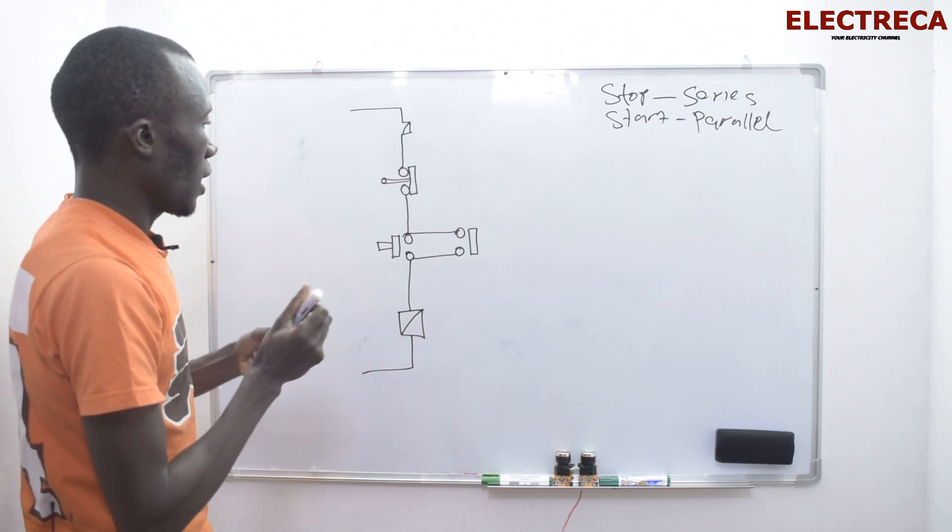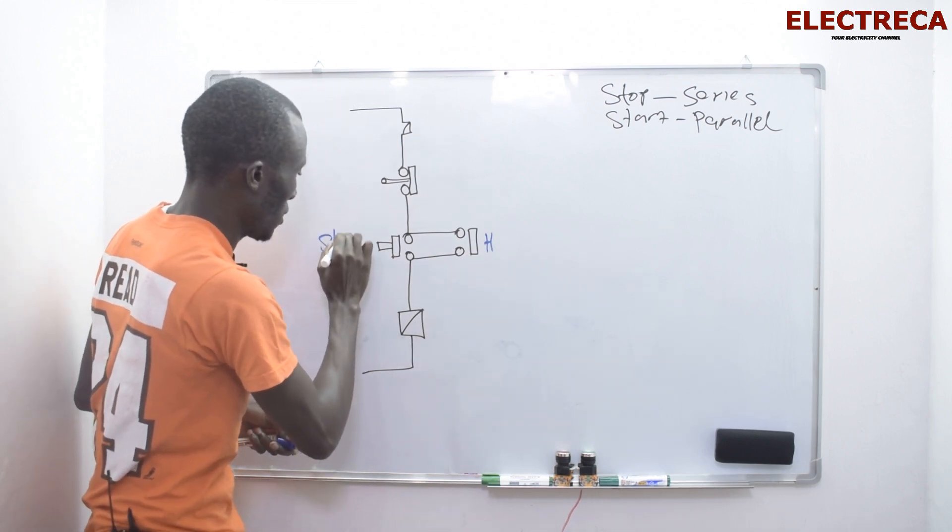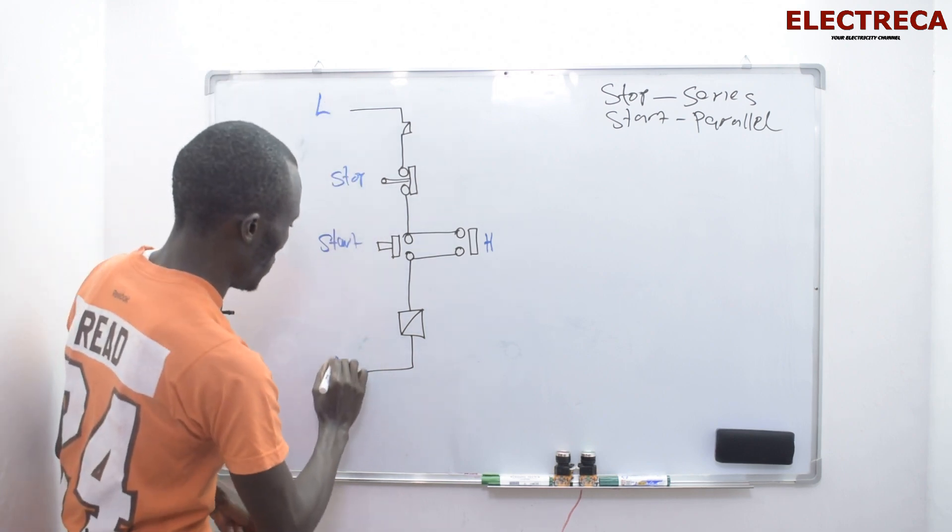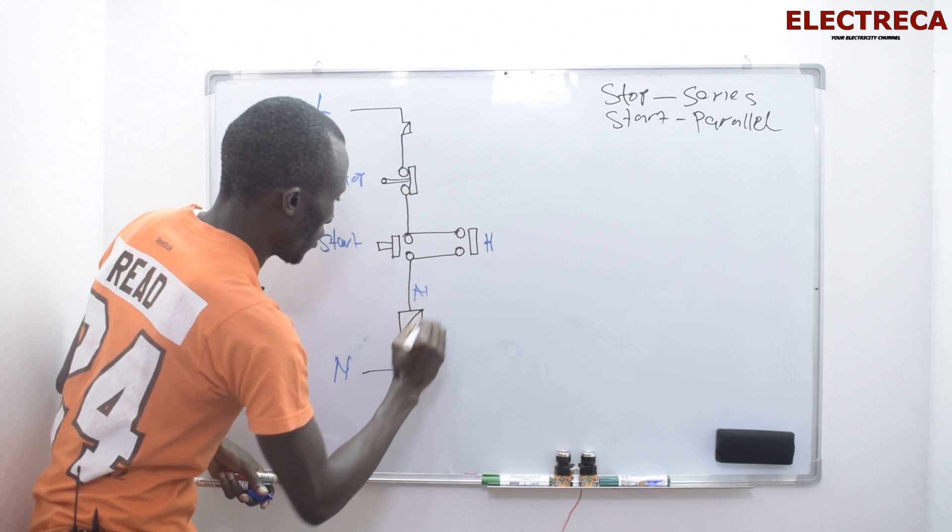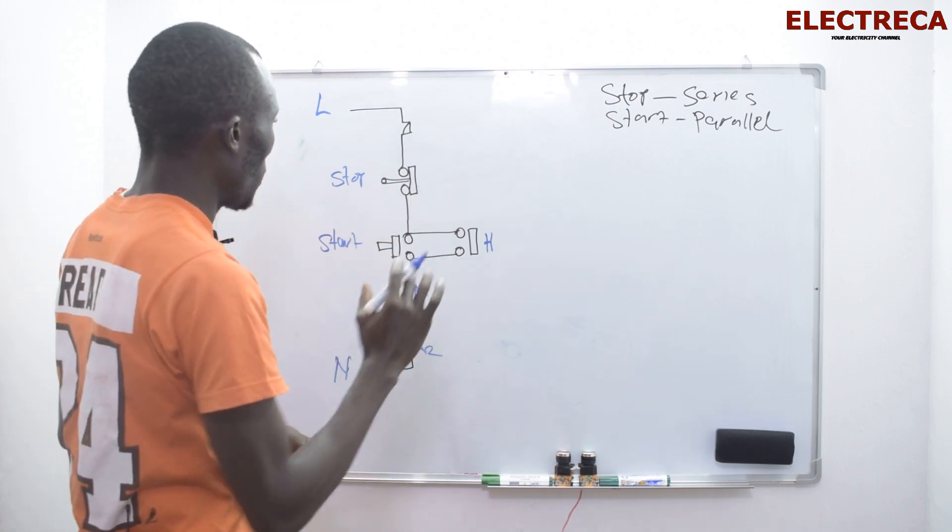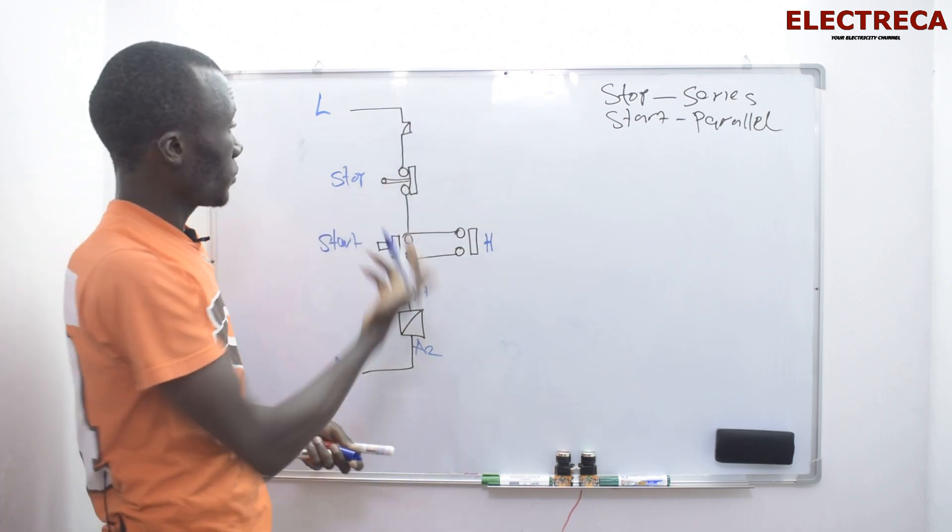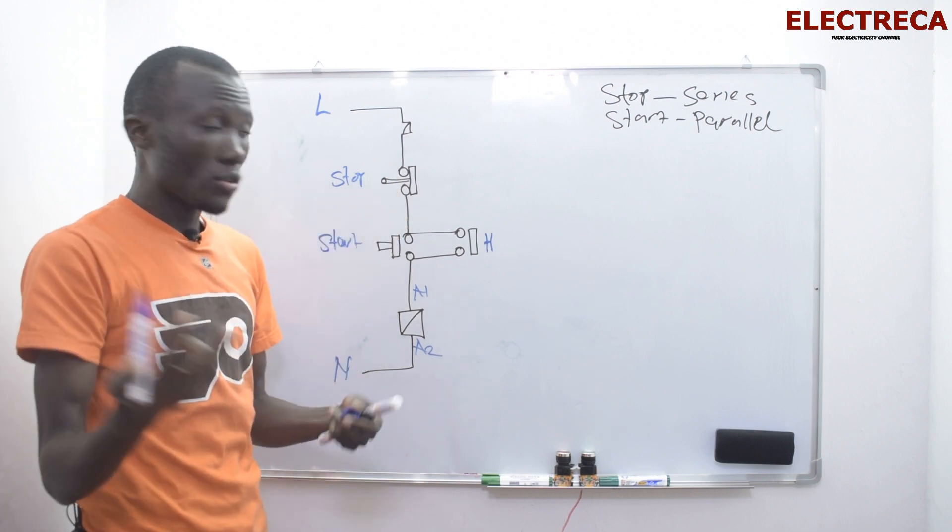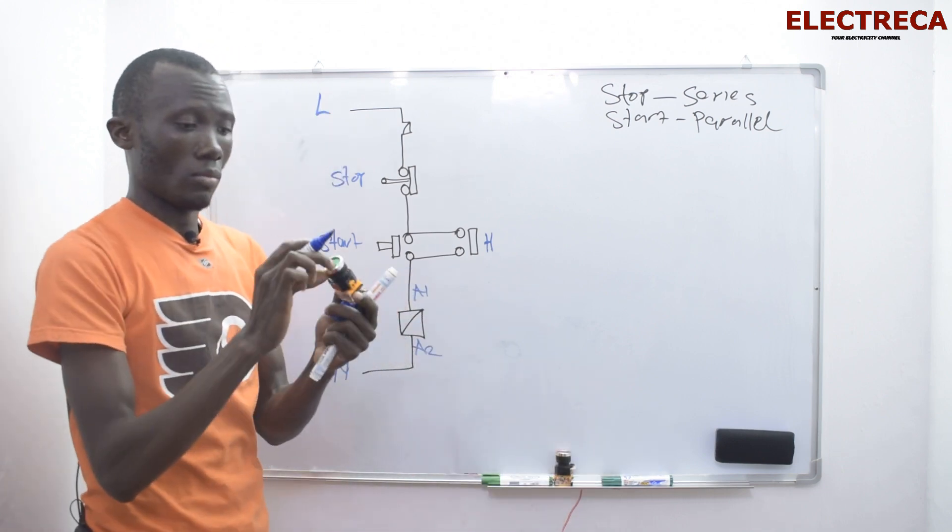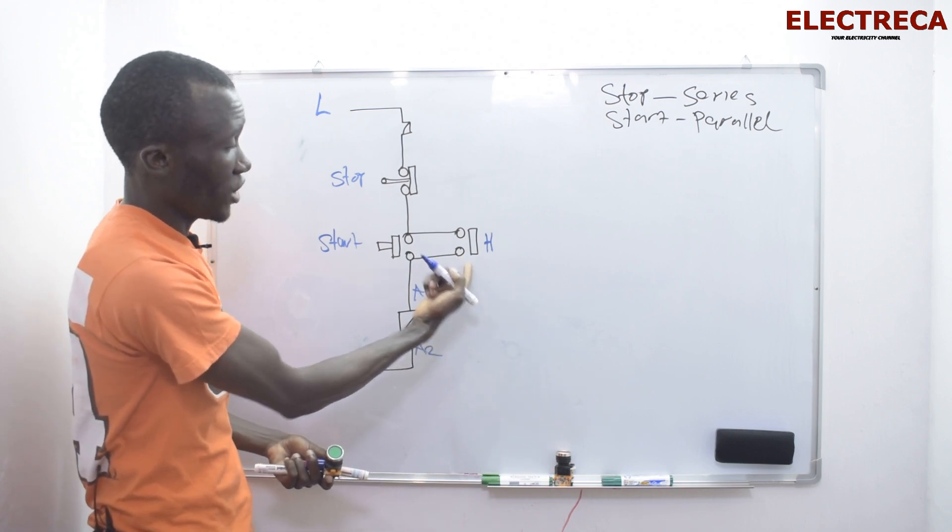And now since it is a self-holding circuit, so this is H the hold, you have your start here and then you have stop, this is your L and then this is N, you have A1 of the coil and you have A2 of the coil. All right, now this is your circuit. You know very well that you have L here goes through the overload relay, through stop button which is normally closed. Now our current pends here. When you press this button here, definitely our coil will get energized and will close the contact H here, and anything connected there will work.